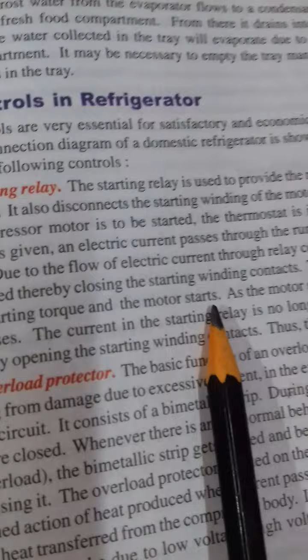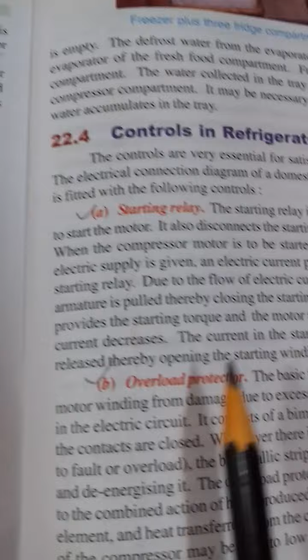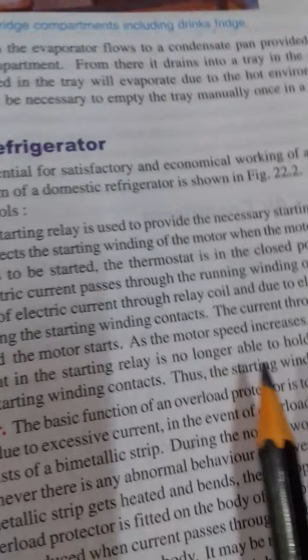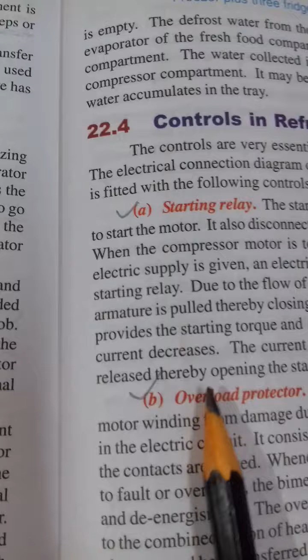As the motor speed increases, the running winding current decreases. The current in the starting relay is no longer able to hold the relay, and it gets released, thereby opening the starting winding contacts. Thus the starting winding gets disconnected.